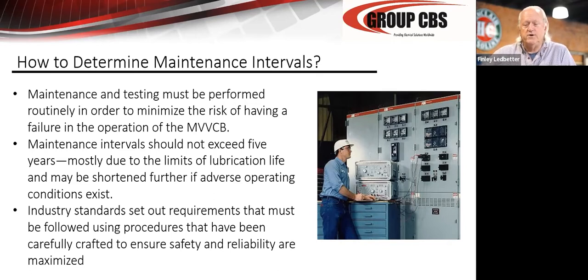There have been lubricant studies done. Tony DeMaria and I wrote a paper for NETA and for IEEE a few years ago, where we did a bunch of advanced lubricant aging tests. We can get that to you if you will request it from Justin. But basically, when you hire a maintenance company, you need to interview them. And there are certain questions you need to ask before they lay their hands on your switchgear. The switchgear is just like your relays. When you have a guy come in to calibrate your protective relays, you're very picky about who you use. You need to be very picky about who you use to maintain and actually do any work on your medium voltage vacuum breakers, because they are just as critical as the relays.